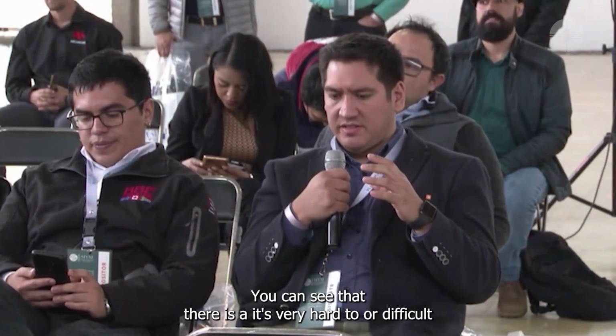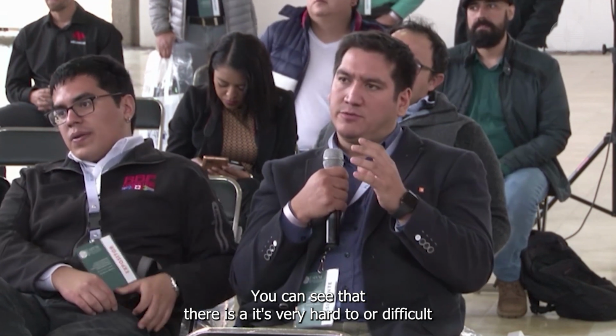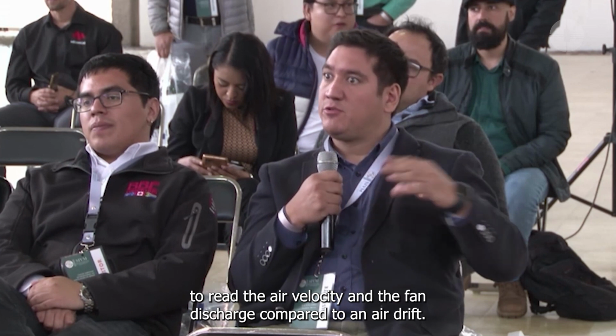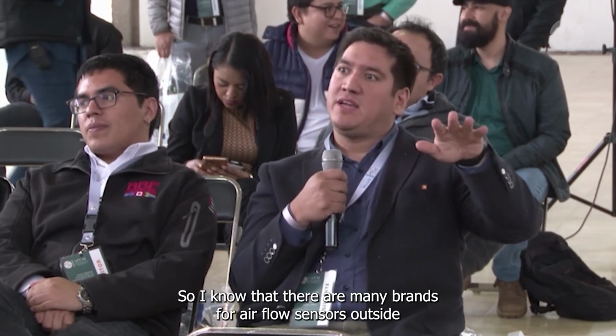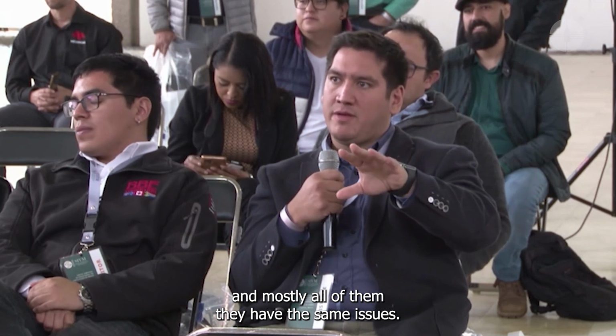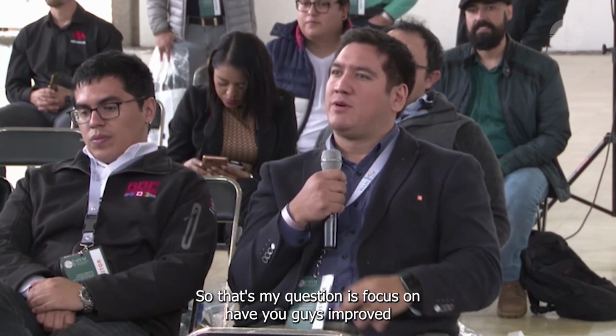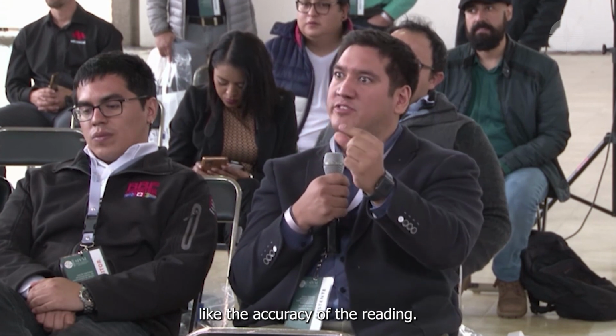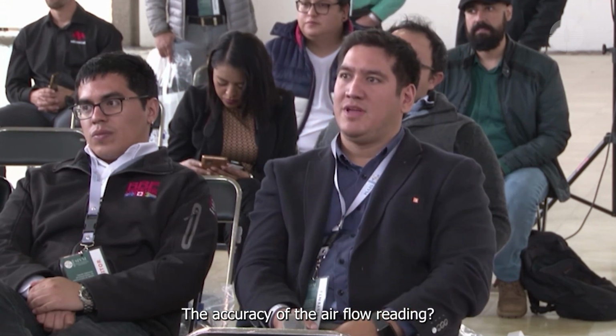No, digital. In terms of communication, I have no issues with that. It's just that on site, you can see it's very hard or difficult to read the air velocity at the fan discharge compared to an air duct. I know that there are many brands of airflow sensors outside, and mostly all of them have the same issues. So my question is focused on, have you improved the accuracy of the airflow reading?